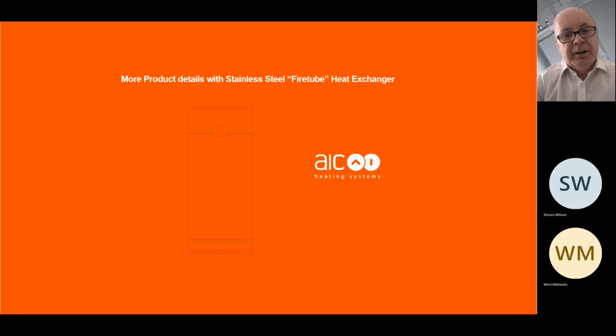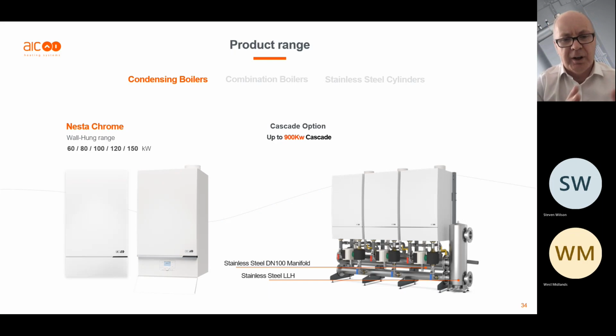Okay, so just to briefly talk a little bit more in depth about the products that you find fire tube technology in. We have the Nesta Chrome range, which is wall mounted. We have standard ranges from 60 to 150 kilowatt. We also do a smaller range, but not on the Cascade rig. And what we tried to do, for all the reasons I spoke about stainless steel, we tried to bring the heat exchanger and the qualities of stainless steel outside the boiler. So you can see here from the whole Cascade system and the hydraulics, they're all manufactured from stainless steel. So again, bringing the qualities of stainless steel outside the boiler as well, and you can see that in the manifolds there and the low loss header.